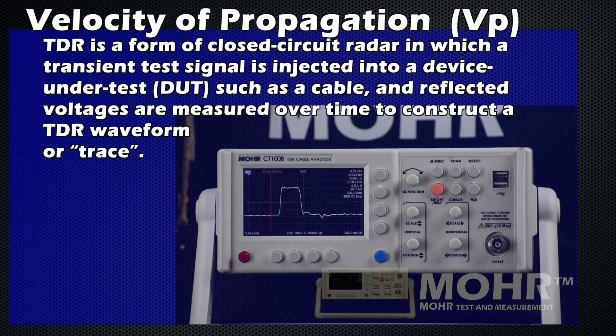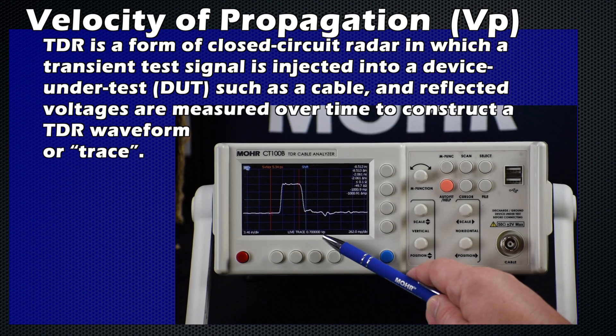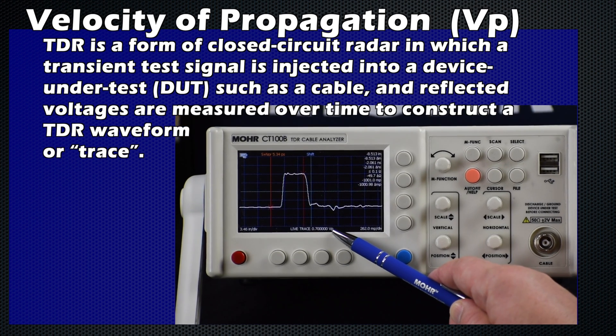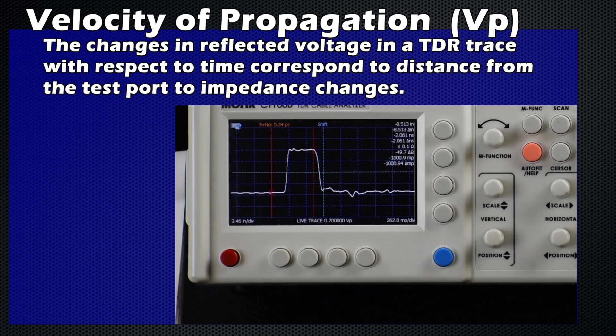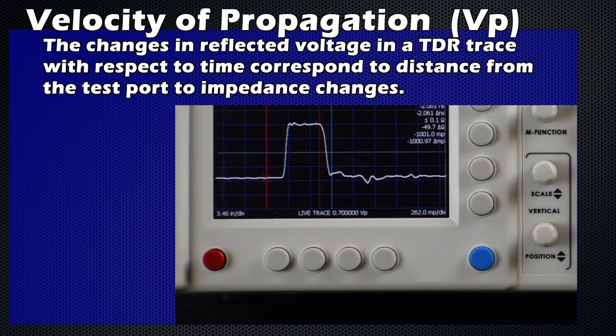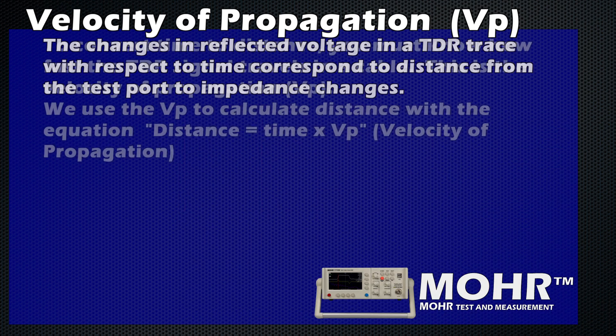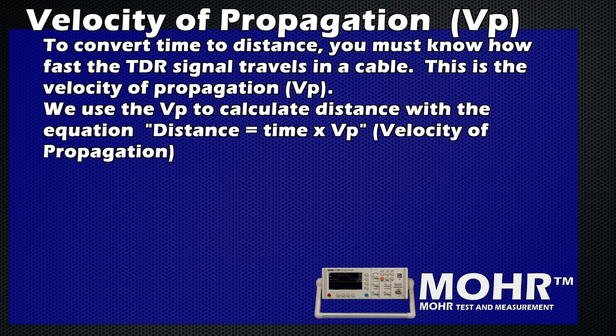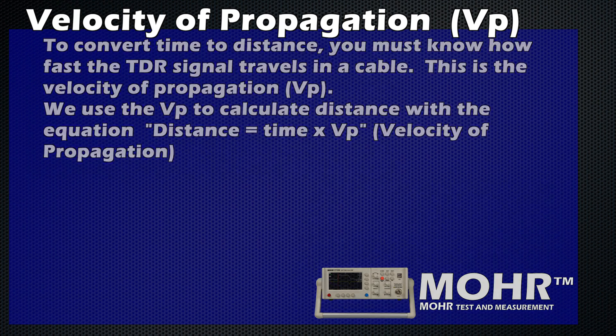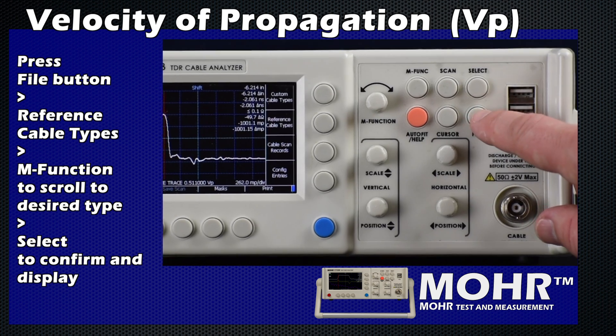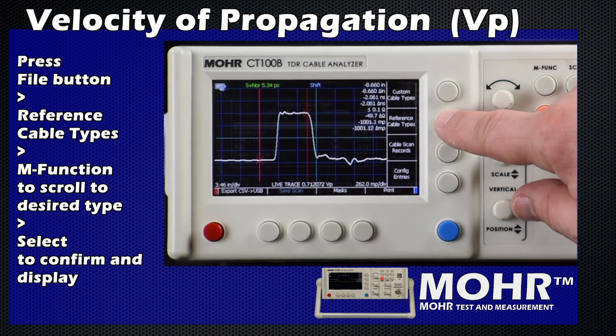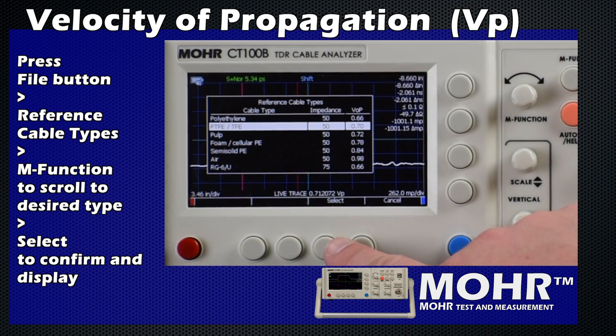First, we need to set the velocity of propagation, or VP. The accuracy of the distance to fault measurement depends on this value being accurate. This is the fraction of the speed of light that electricity travels in this cable. You can get this number from your manufacturer in the CT100B file function, or you can set the VP manually.